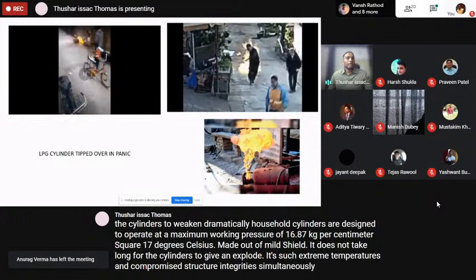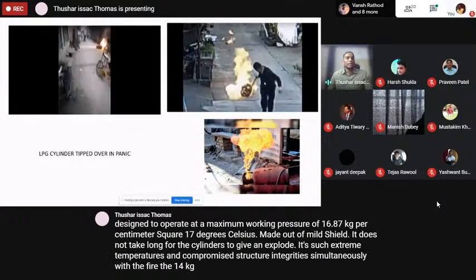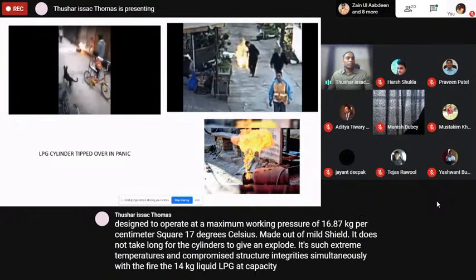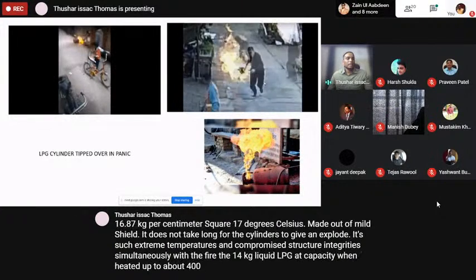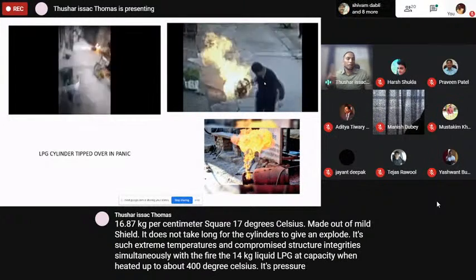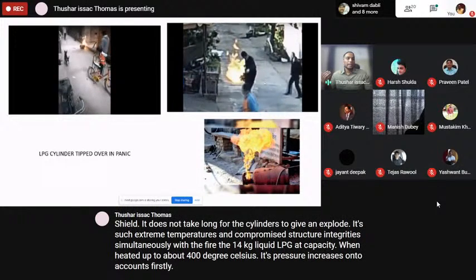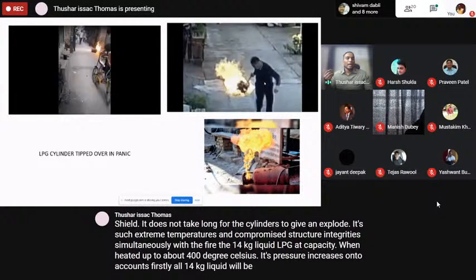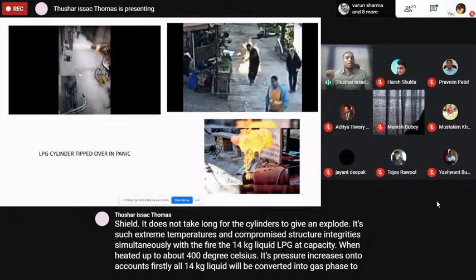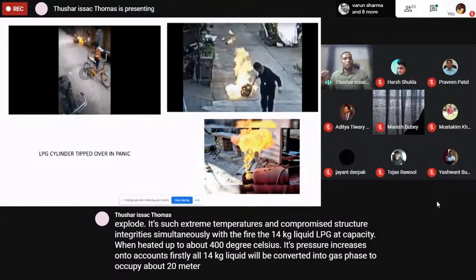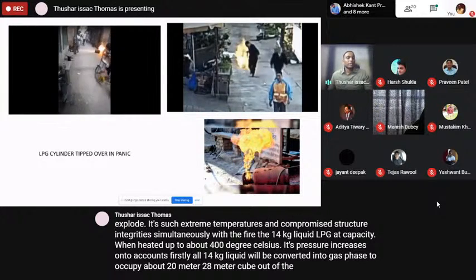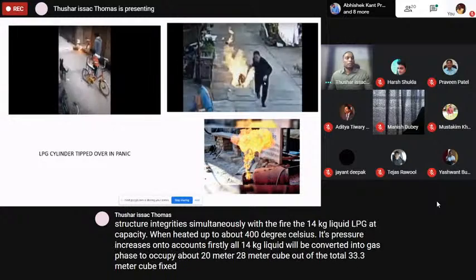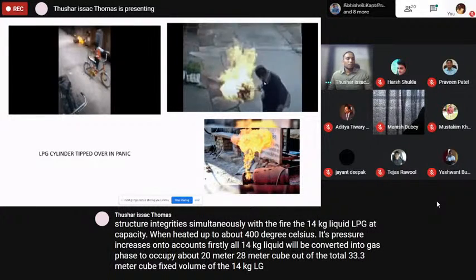Simultaneously, with the fire, the 14 kg liquid LPG at capacity, when heated up to about 400 degrees Celsius, its pressure increases on two accounts. Firstly, all 14 kg liquid will be converted into gas phase to occupy about 28 meter cube out of the total 33.3 meter cube fixed volume of the 14 kg LPG cylinder.